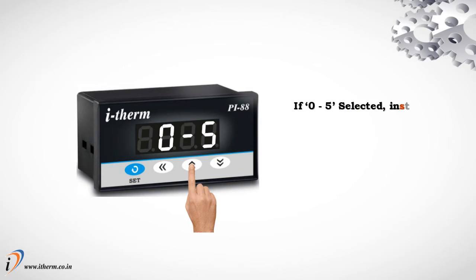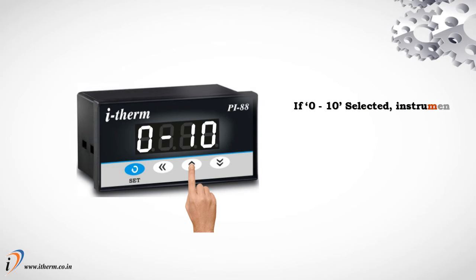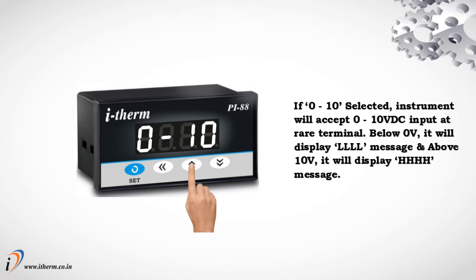If 0 to 10 is selected, the instrument will accept 0 to 10 volt DC input at the rear terminal. Below 0 volt, it will display an LLLL message, and above 10 volt, it will display an HHHH message.